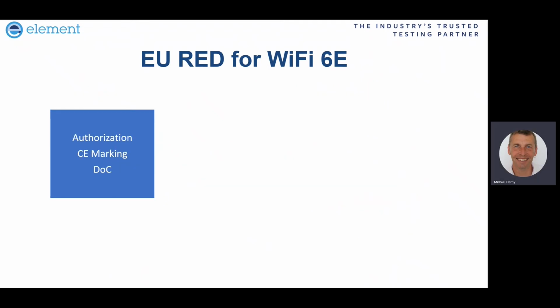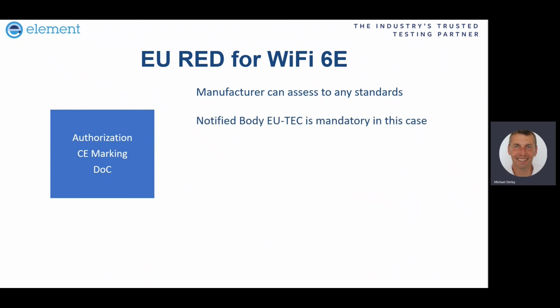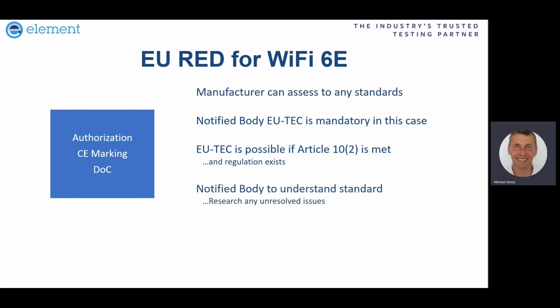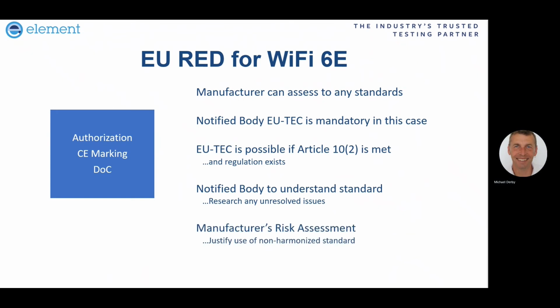With regard to authorizing and CE marking and the manufacturer's declaration of conformity, the manufacturer can assess to any standard, so it doesn't matter that the standard is draft or at the ENAP stage. The notified body type examination certificate is mandatory for Wi-Fi 6E at this time because the standard is not on the official journal. The RED states that the notified body can only issue a TEC if the product can be used in the EU and the regulation exists for it. Well, the Commission decision is there and all the countries allow it, so we know that we can proceed with that. The standard isn't listed on the official journal though, and the notified bodies are expected to understand the situation with the standard and be aware if there are any problems. The manufacturer's risk assessment must always include details if the manufacturer has used a non-harmonized standard. For example, the manufacturer is expected to justify why they thought that standard was the correct one. And that's because the standard does not provide presumption of conformity. Again, if this is confusing to you, please get in touch.